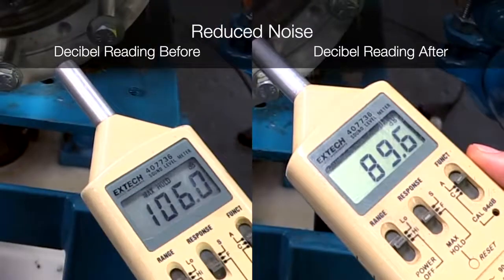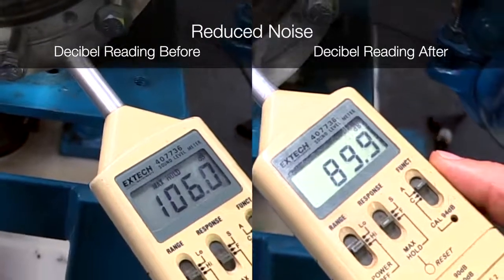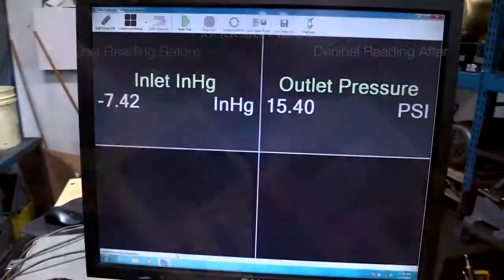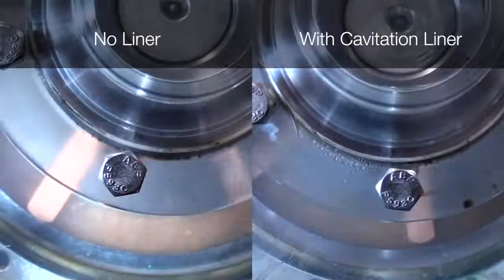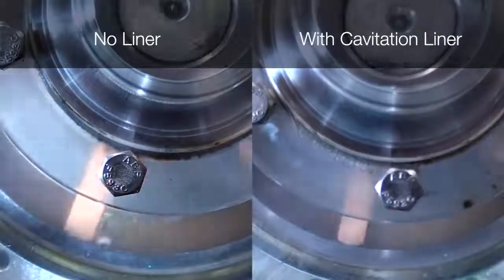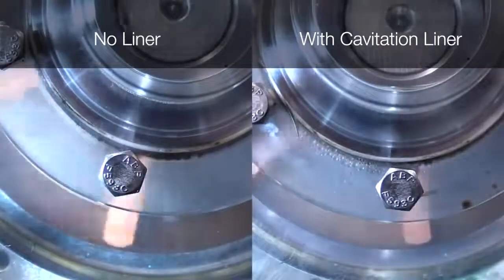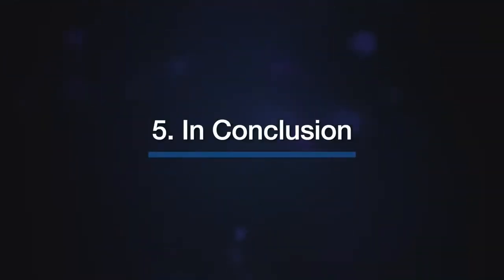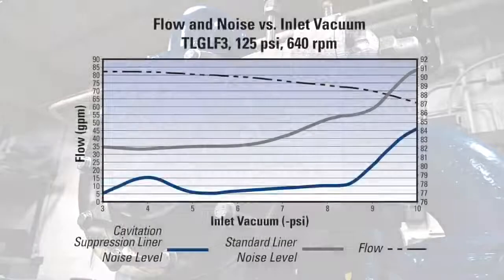The cavitation suppression liner makes the pump perform smoother and quieter under identical conditions. Here we see the difference side by side. The pump on the left has no liner, while the pump on the right is equipped with a cavitation suppression liner. To summarize our findings, the unique characteristics of the Blackmer cavitation suppression liner can greatly reduce the damaging effects of cavitation by managing the entrained gas bubbles inside the pump.